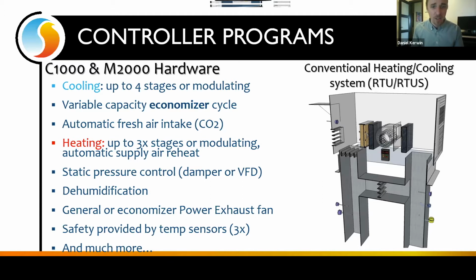So no matter what the heating source of the unit is, we can control it. Out of the box, this controller is able to control static pressure as well. So if there's a bypass damper or a variable frequency drive, we can take care of it. We have an embedded dehumidification sequence as well. And we can also take control of exhaust fans, whether they're following a general schedule, or in case there's a power exhaust within the unit to control building pressure. So all these components, we are able to handle with our single rooftop controller right here.